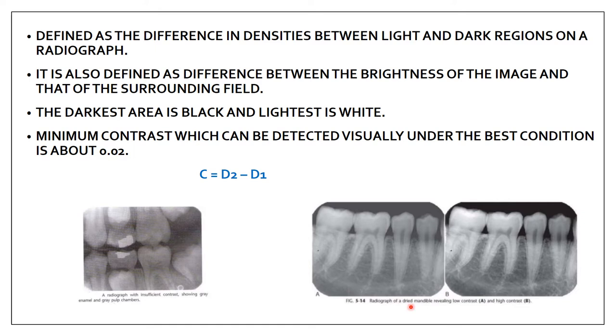Here is an example showing the difference in contrast. This one is having low contrast and this film is having high contrast. High contrast is when it appears more black and white, and low contrast is when you see the image having more of a grayish color. The minimum contrast which can be detected visually under the best conditions is about 0.02. The formula for contrast is C = D2 minus D1.